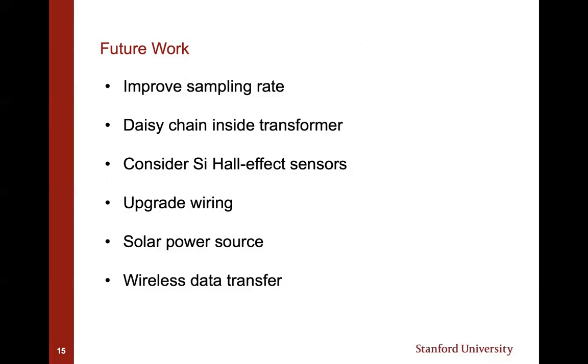In this prototype, each sensor required 7 wires, so a total of 42 through the bucket for 6 sensors. Now, using SPI interface, each sensor must have its own chip select and data ready line, but everything else can be shared. So daisy chaining inside the transformer would mean there's only 17 lines rather than 42 going through the bucket wall for 6 sensors. Our lab chose to investigate indium aluminum nitride, gallium nitride sensors in particular because they had proven themselves durable and reliable in our lab's previous work.